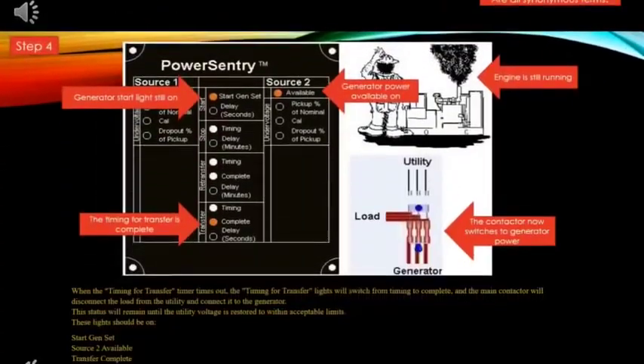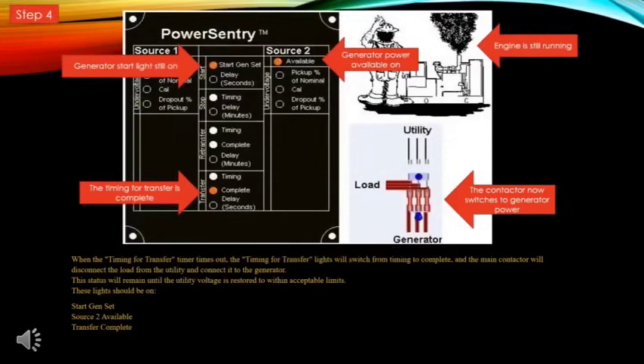Step four: when the timing-for-transfer timer times out, the timing for transfer light will switch from timing to complete, and the main contactor will disconnect the load from the now-dead utility and connect it to the generator. This status will remain until the utility voltage is restored to within acceptable limits. The generator start light is still on, generator power available light is still on, and smoke is still coming from the engine. The timing for transfer is now complete, and the contactor has switched from the utility over to the generator power.